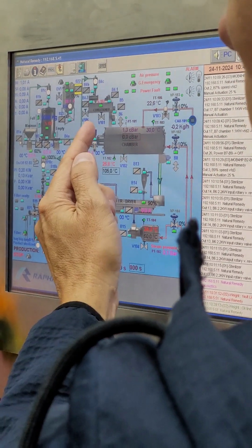Then what time will it start? Depends on how many times it takes to reach. So each day is different. Do it like this. The advantage is stabilizing basically the material temperature and everything, and then inject the steam so that the sterilization is very effective.